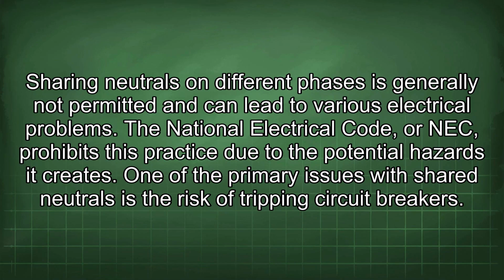Sharing neutrals on different phases is generally not permitted and can lead to various electrical problems. The National Electrical Code, or NEC, prohibits this practice due to the potential hazards it creates. One of the primary issues with shared neutrals is the risk of tripping circuit breakers.